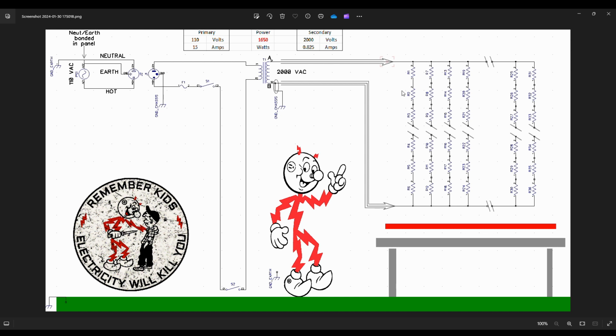Let's suppose this connection has failed. That means there's a pathway through the block of wood, through your workbench, whether it's metal or wooden, I don't care. So the current can come through this setup into your workbench to ground, and follow along here - it's traveling along ground. This ground symbol is the same potential as that ground symbol. Your neutral line and your earth line are both at ground potential, very close to it.